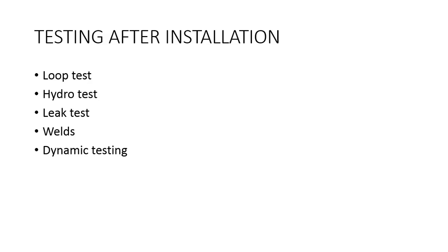Next is the hydro test. The valve is hydro tested at valve manufacturer location. However, after the valve is installed, one must check the complete reliability of pipe and valve. If improper compression of gasket is there between the pipe flanges and the valve flanges, it may lead to leakages, external leakages.